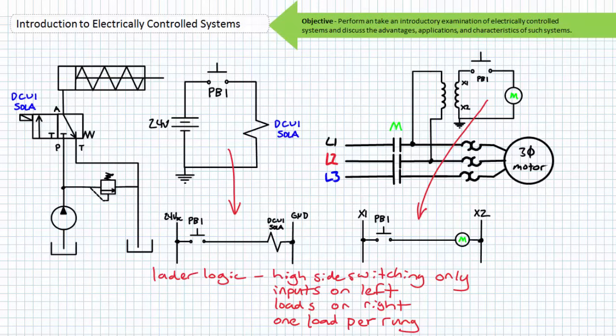The high side is the left-hand vertical upright. The right side is the low side or neutral vertical upright. A switch, switches, or other input devices on the left selectively connect or disconnect an electrical load on the right via conductive rung on the ladder. Inputs on the left, electrical loads on the right.